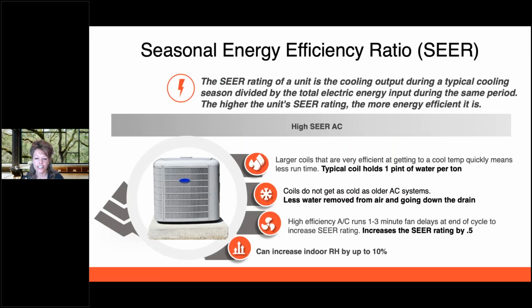So our SEER ratings keep getting higher and higher. We are getting really energy efficient HVAC equipment. They're using larger coils that are very efficient at cooling the air, resulting in less runtime. These larger coils hold about a pint or a pound of water per ton. So if you have a 3-ton system, you've got 3 pints of water on the coils. The coils don't get as cold as they used to.